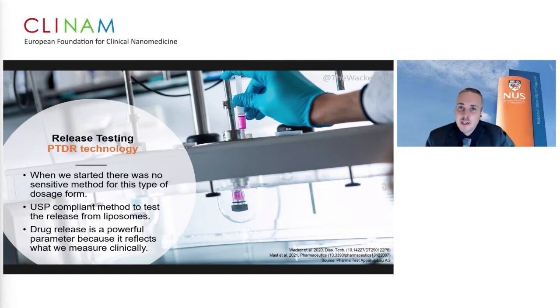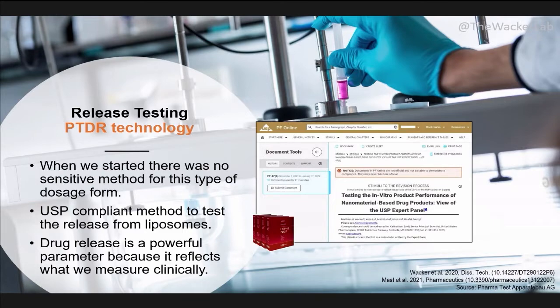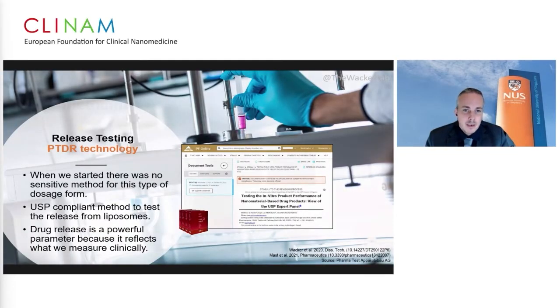Because from the perspective of a drug company, of course, it makes no sense if you have a method which only works in one lab and not in others. So now that we are able to measure the drug release, and I can really say we set standards here, we also included all the validation protocols for this equipment into a Stimuli article for the USP, which means we hope that soon our equipment will appear as an international, or at least national, standard, first in the United States.